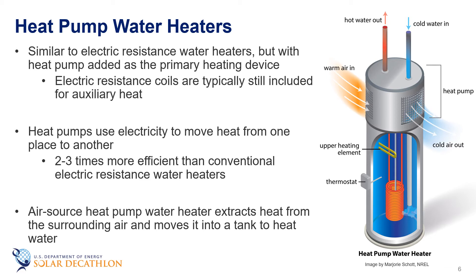As heat pumps extract heat from the surrounding air, they will cool the surrounding space. If located inside the house, the heat pump will cool and potentially dehumidify the house. So not only do you get the benefit of heating hot water at two to three times the efficiency of an electric water heater, you also get cooling and dehumidification. There is no free lunch, however — if the space needs heat, you need another source, either a heat pump that brings in heat from outdoors or a typical fossil fuel boiler or furnace.